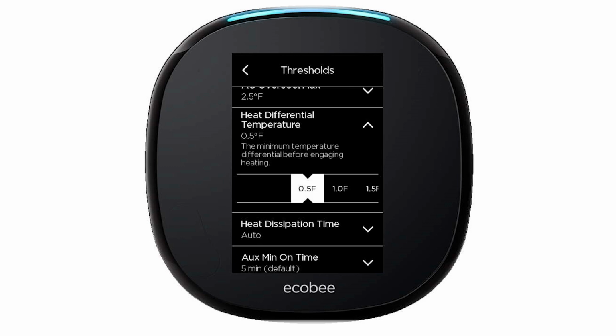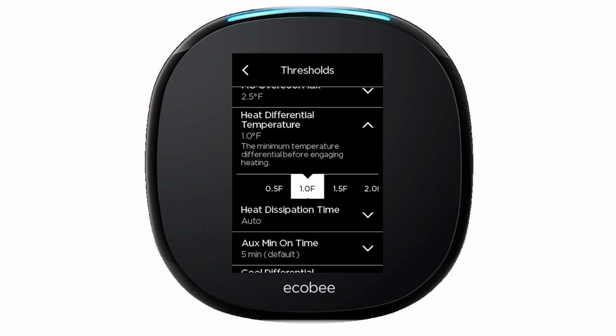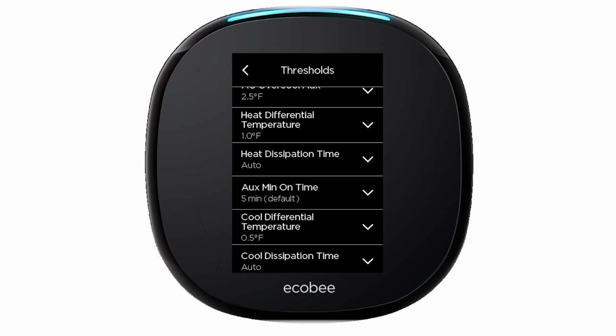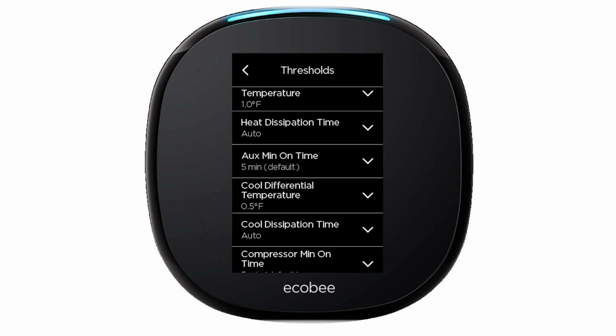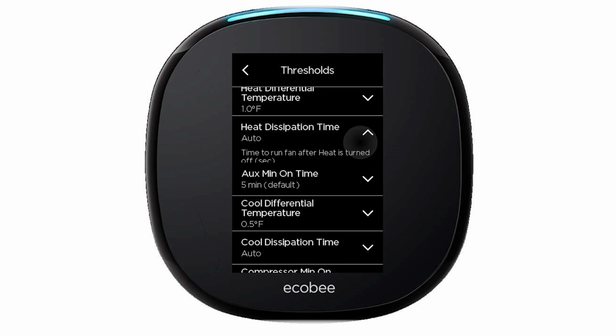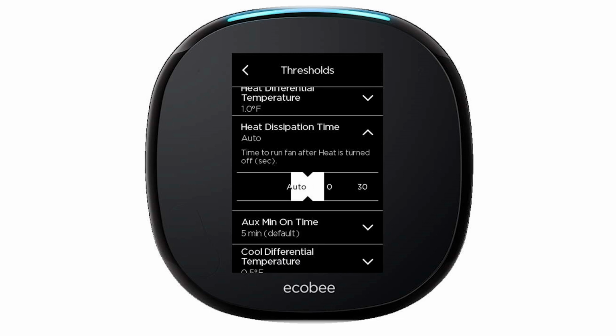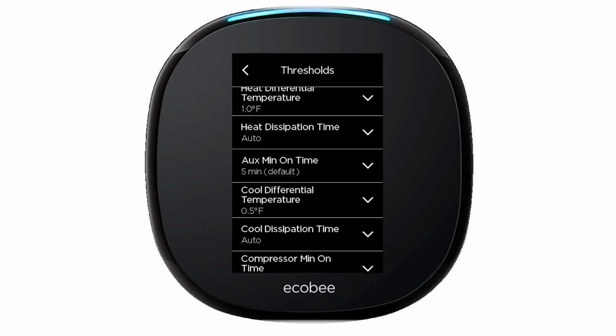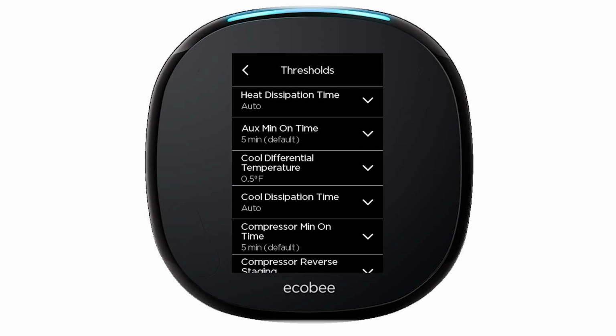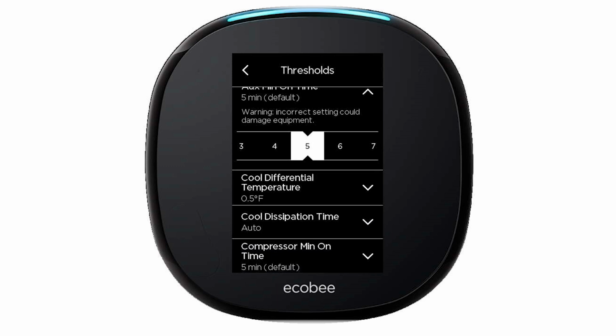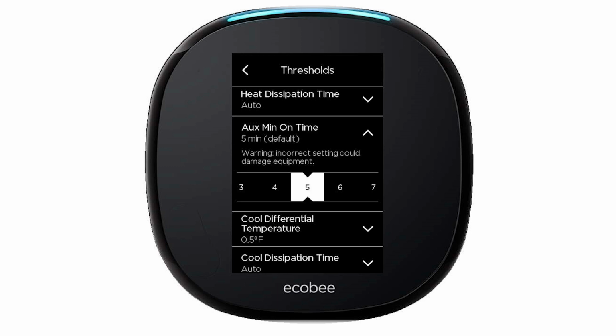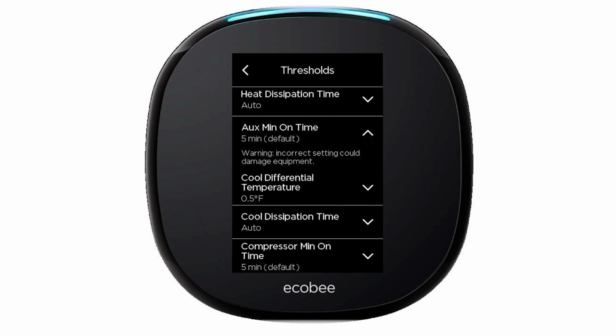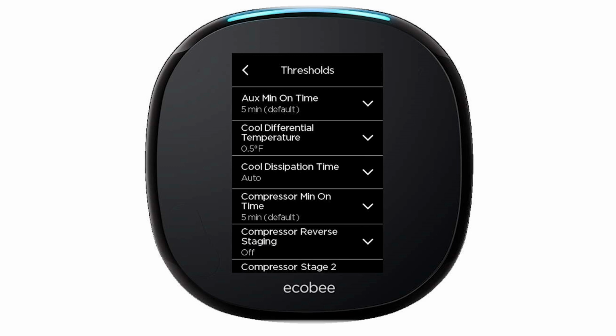You can adjust your differential. This is going to be the minimum differential before the heating kicks back on. So in between cycles, how far it's going to let that room temperature creep before the furnace runs again, or the heat pump. Dissipation time. So after the heat call is off, how long do you want that fan to keep running to keep that warm air flowing? Your auxiliary minimum on times, right? So you can adjust these, going to default to 5.